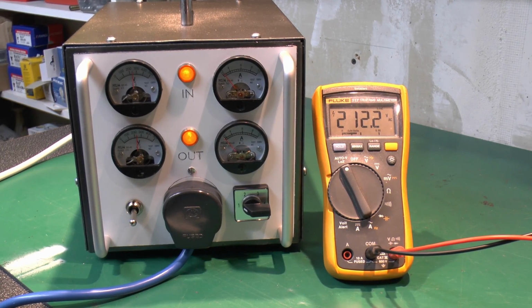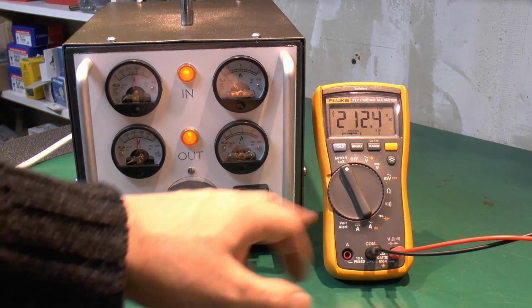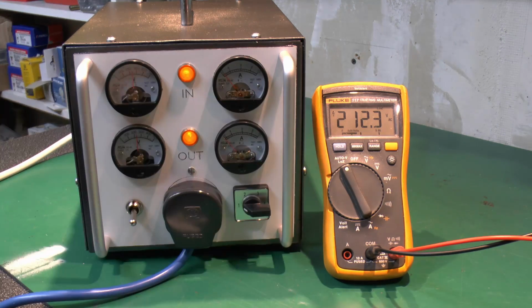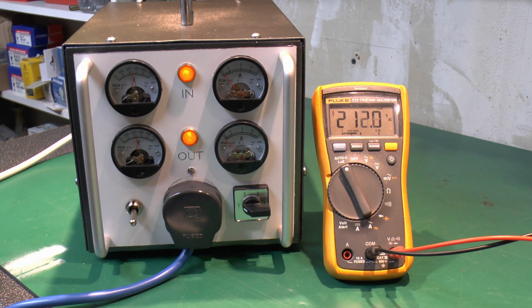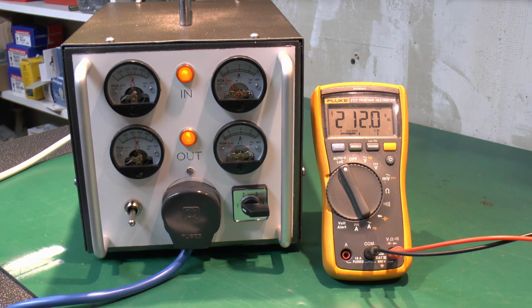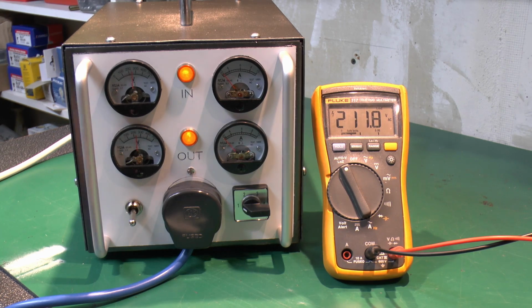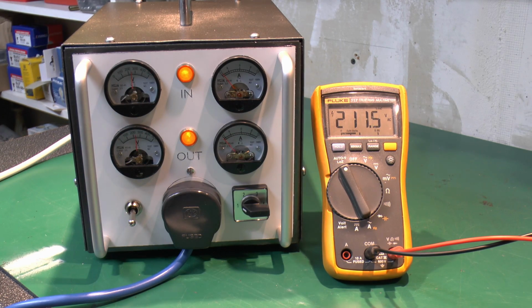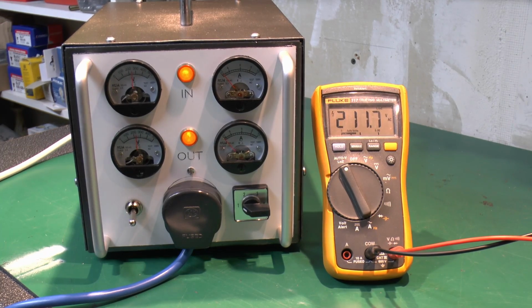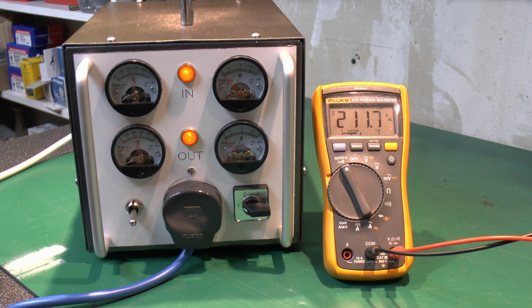So here it is in the on condition, and we can see the two voltages marked there - the input and the output. In this case we're on the bottom one, which reduces the voltage to about 212 on the output, connected to this blue lead. The voltage going in is the usual 245 or so, and the output is slightly lower. Current is zero because there's no load attached other than this meter, but if we plugged in a moderate load that would show.